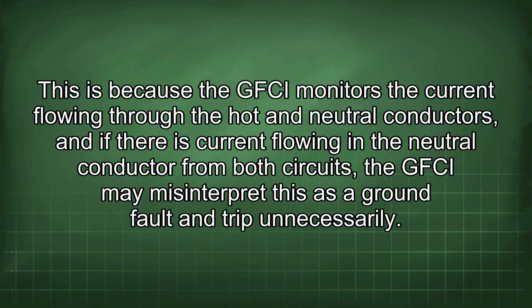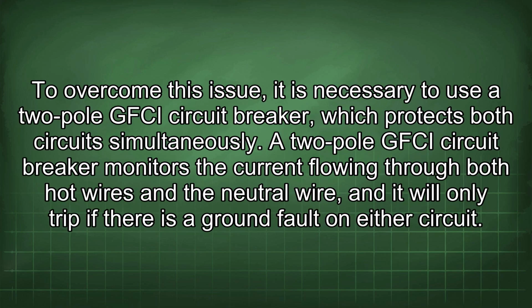This is because the GFCI monitors the current flowing through the hot and neutral conductors, and if there is current flowing in the neutral conductor from both circuits, the GFCI may misinterpret this as a ground fault and trip unnecessarily. To overcome this issue, it is necessary to use a two-pole GFCI circuit breaker, which protects both circuits simultaneously. A two-pole GFCI circuit breaker monitors the current flowing through both hot wires and the neutral wire, and it will only trip if there is a ground fault on either circuit.